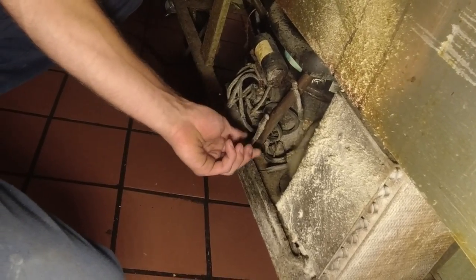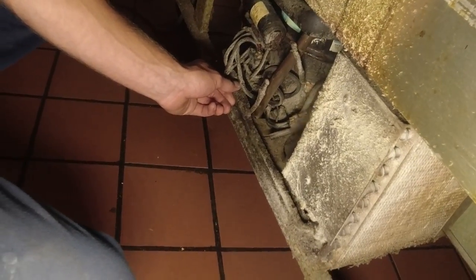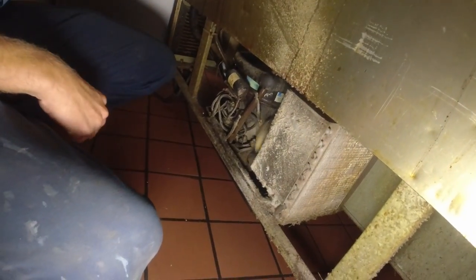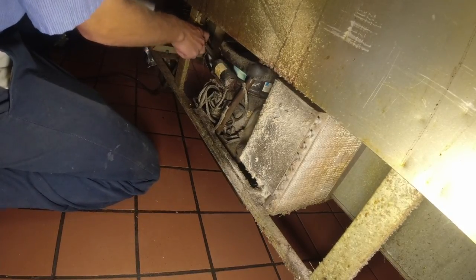Feel the drier there - be careful, there's a cover missing on the compressor. Does it feel warm? It's above room temperature, yeah. So we're probably feeding okay - I doubt we're low on charge. It could have an airflow issue or dirty coils. Sometimes a dirty condenser coil builds up artificial head pressure which brings everything up and makes it seem like it's low on charge.